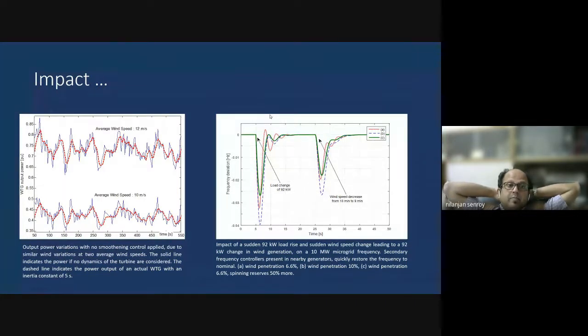If the average wind speed is 12 meters per second, the smoothing is less, while at 10 meters per second, the smoothing is more. We have injected the same random variations in wind speed at 12 meters per second and 10 meters per second, and we find that the wind farm output is smoother at 10 meters per second. Similarly, if you compare a 92 kilowatt change in wind generation with a 92 kilowatt change in load in a small microgrid, you will find that the load causes a deeper change in frequency compared to the wind turbine, and this is also a result of the shaft inertia.